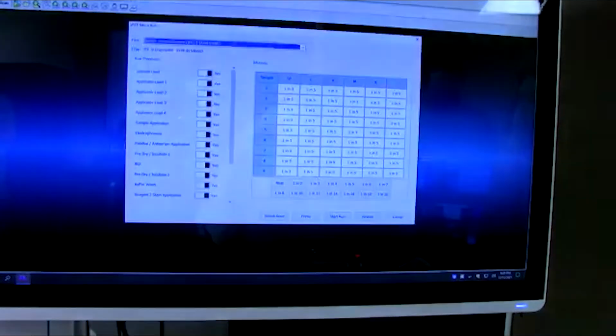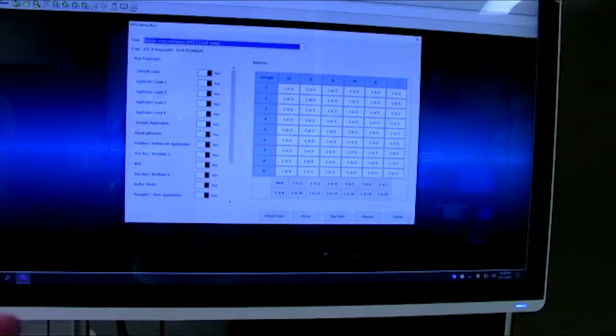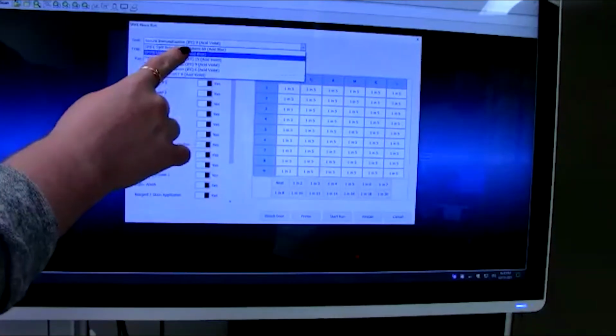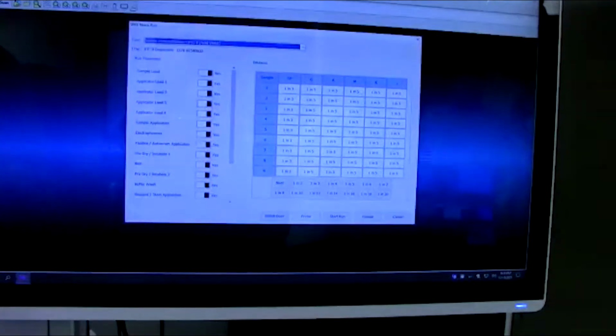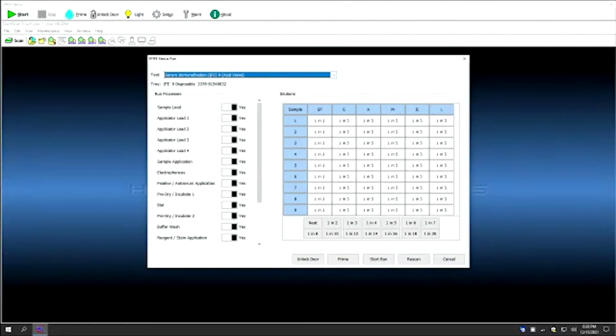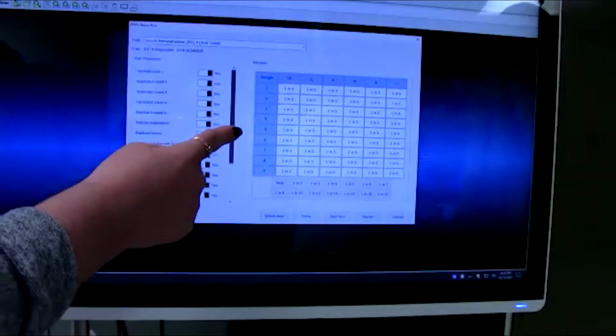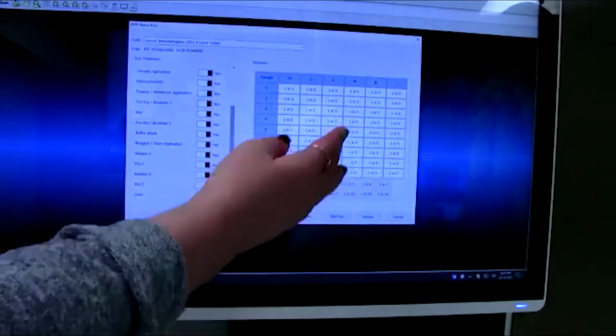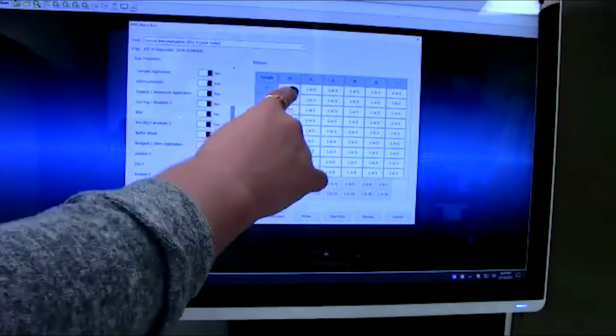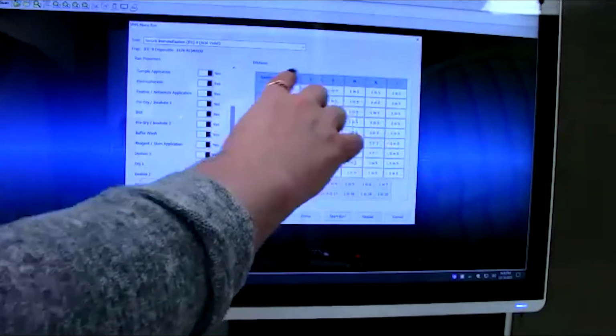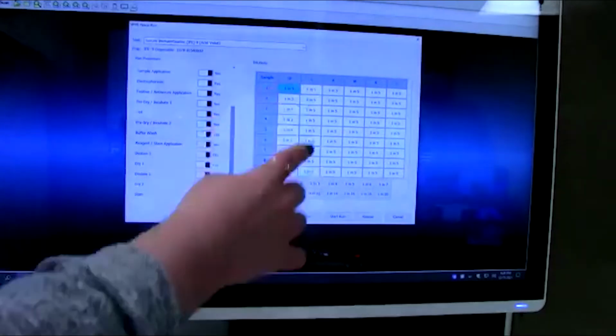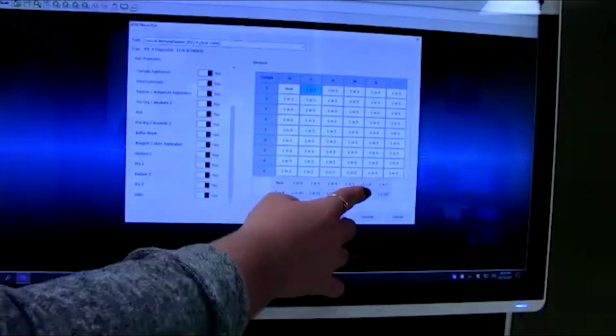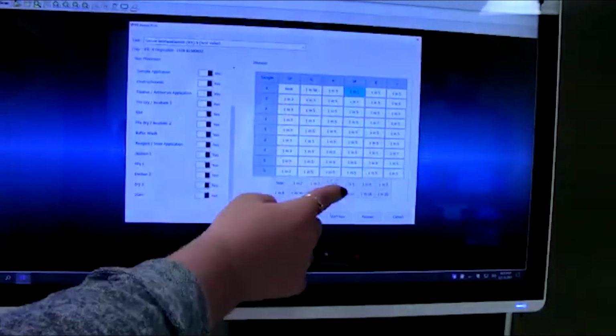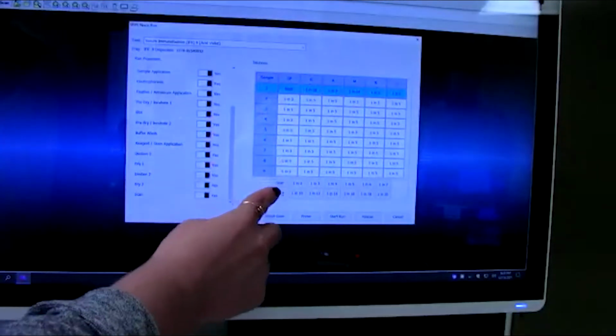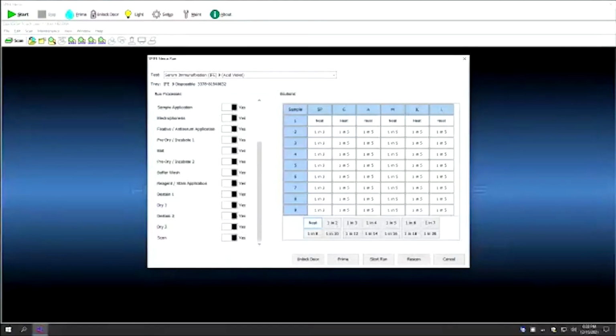Great. All right. So to start up a run, you'll just press your start bar here, and you'll see a menu that includes a drop-down bar where you can select the test that you would like to run. Right now, I'll go with an IFE 9 because that's what I have set up on the platen. And then here you can turn on and off each process individually, and you can control your dilution scheme. So the normal scheme is set up to be 1 to 3 in the fixative lane and 1 to 5 in the rest. But that's customizable. To do that, you just highlight and select new dilutions for any lane of any sample, or you can highlight the entire lane and choose a dilution for the entire sample.